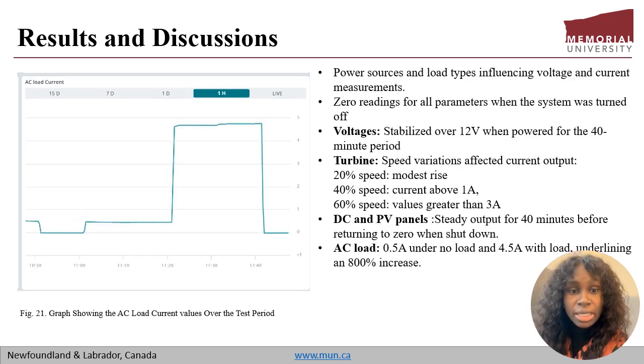This graph, fig 21, shows the AC load current where the first 10 minutes from 10:50 to 11 was of 0 value, and then we turned on the inverter, but we didn't connect the load yet. We can see about 0.5 amps being recorded for the next 20 minutes, and then when the load was brought on, we see about an 800% increment in the load values, from 0.5 to about 4.5 amps.